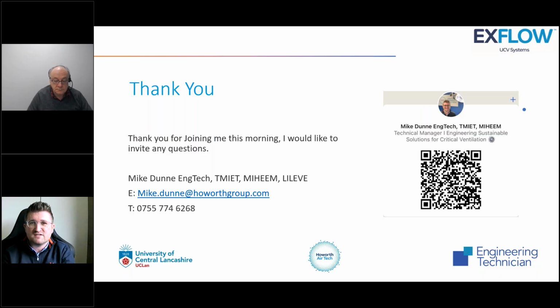So when Malcolm wrote the HTM, he put DPC as an option for filtration testing, because you can drop the efficiency of a HEPA filter down to E11 in a conventional operating theatre. And if you've got a filter efficiency of E11, then you can't DOP it because the DOP will bypass the filter. So in that instance, we carry out a DPC test, which we demonstrate on CPD day. Once that test has been done, the filter frame has been sealed and everything from an integrity point of view is there or thereabouts. You would then carry out a secondary balance of the ventilation system.